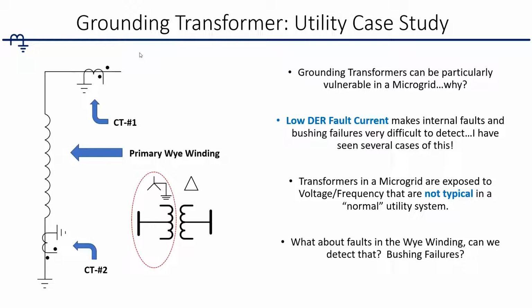One other thing I think people miss that I always like to pass along is that transformers in a microgrid are exposed to voltages and frequencies that are not typical in a utility system. The frequencies are very highly regulated in a utility system when it's grid connected. Utilities do a great job at that. In a microgrid, when you have droop controls and other things like that, not so much. They're getting exposed to things that are a little bit more atypical, so you're going to see higher failure rates, and that's what we are seeing. We're seeing higher failure rates with that.